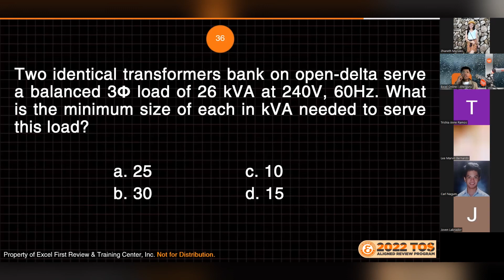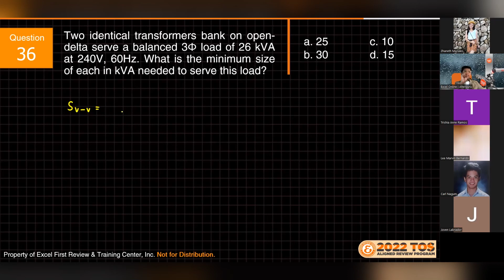sa open delta kasi, di ba, pag balanced na three-phase siya at hindi open delta, let's say delta-delta siya, kung balanced ka, ang kinikarry ng isang transformer is over 3 lang. But this time, pag meron kang balanced na three-phase load na naka-open delta, we divide it by square root of 3 instead, hindi by 2, by square root of 3.